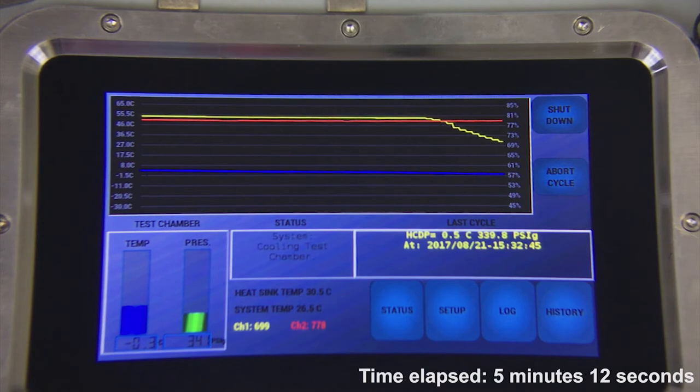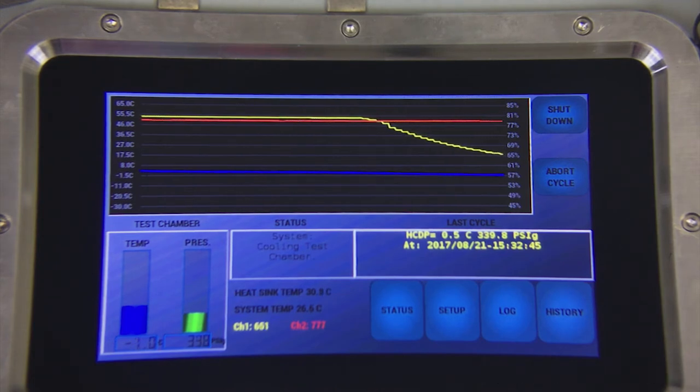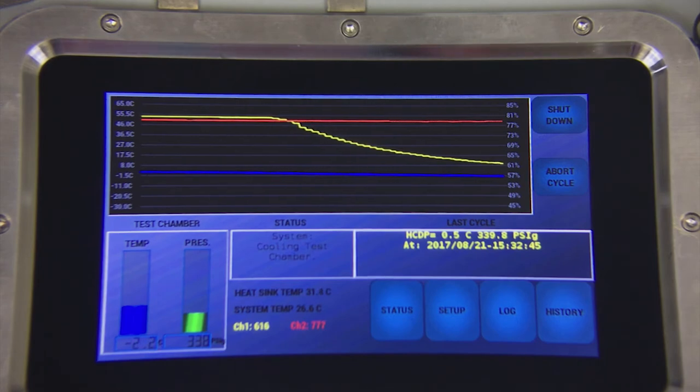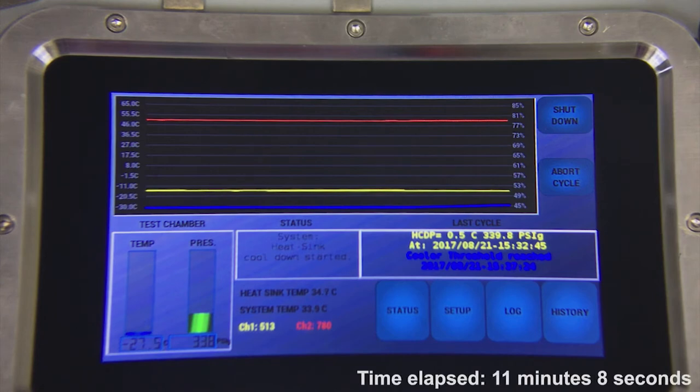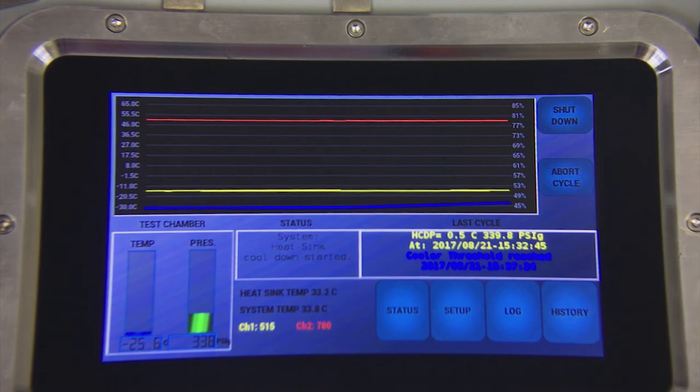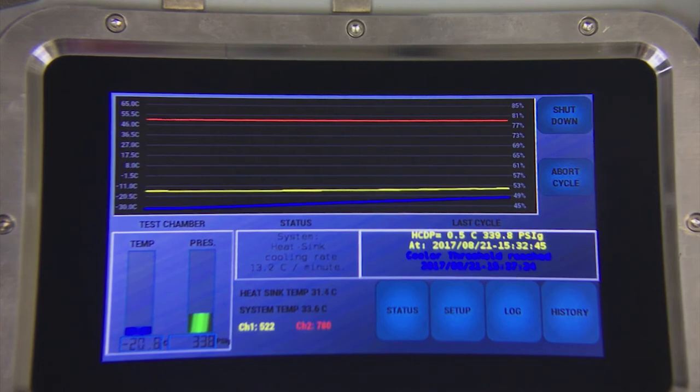Once a hydrocarbon dew point is found, the test results will be posted in the last cycle box. The unit will continue cooling until it finds another dew point or reaches the cooling limit. The test cycle has ended and now the system is in heat sink cool down mode. In order for the next test cycle to begin, all the temperatures including the crystal chamber, heat sink, and system temperature must return to equilibrium, as well as the recovery of detector signals of channels 1 and 2.